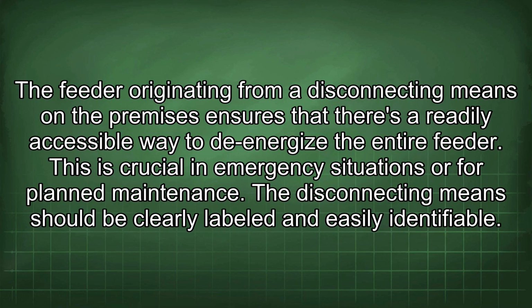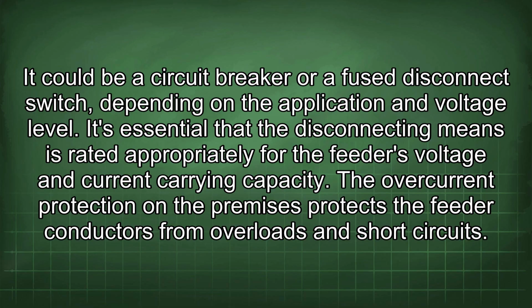The feeder originating from a disconnecting means on the premises ensures that there's a readily accessible way to de-energize the entire feeder. This is crucial in emergency situations or for planned maintenance. The disconnecting means should be clearly labeled and easily identifiable. It could be a circuit breaker or a fuse disconnect switch, depending on the application and voltage level. It's essential that the disconnecting means is rated appropriately for the feeder's voltage and current carrying capacity.